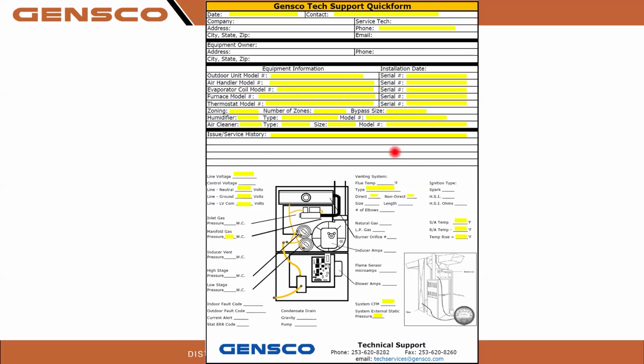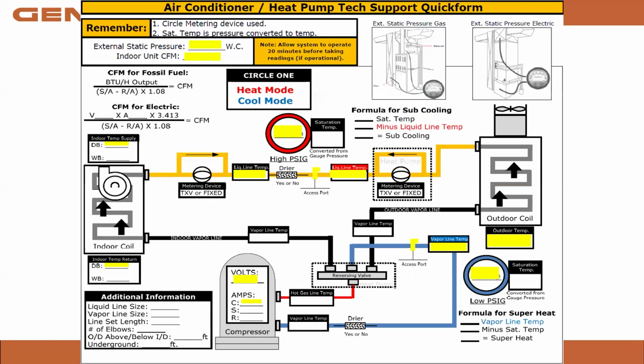First time, it's hard. Second time, it gets a little bit easier. Third time, they're starting to see patterns. Fourth time, fifth time, sixth time, you will start seeing the problem as you're filling in the data. So this is a great tool to educate your brain. When I started out, I had my little notepad I'd carry in my pocketbook. I'd write down, as I had perfect systems, outdoor temperature, pressures, gas line temps, superheat, subcool. I'd refer to those perfect temperatures when I had issues. Again, this tells a lot. These quick charts have our CFM.